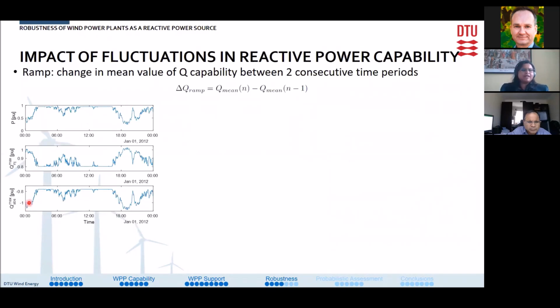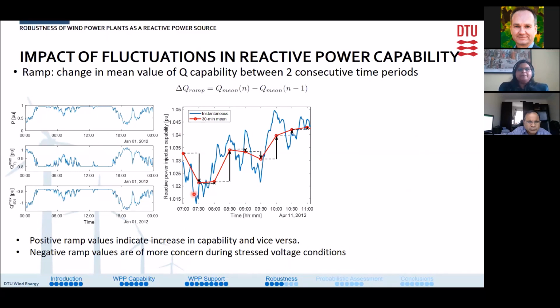Here we can see the fluctuations in reactive power with respect to fluctuations in wind power. Now, it looks nice, but it is difficult to understand. And in order to understand and quantify these reactive power capability fluctuations, we used ramp. This is an example of a ramp calculated for a time period of 30 minutes. So here the black upward arrows denote positive ramp values, which indicate that the reactive power capability of the wind power plant is increasing. The downward facing black arrows denote negative ramp values, which means that the reactive power capability is decreasing. Now, during stressed voltage conditions, we are more concerned about decreasing reactive power capability.